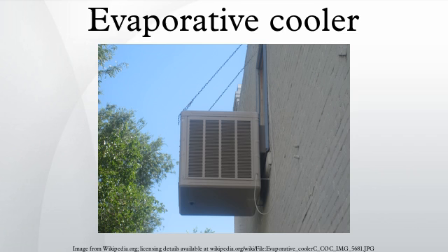An evaporative cooler is a device that cools air through the evaporation of water. Evaporative cooling differs from typical air conditioning systems, which use vapor compression or absorption refrigeration cycles. Evaporative cooling works by employing water's large enthalpy of vaporization. The temperature of dry air can be dropped significantly through the phase transition of liquid water to water vapor, which can cool air using much less energy than refrigeration.